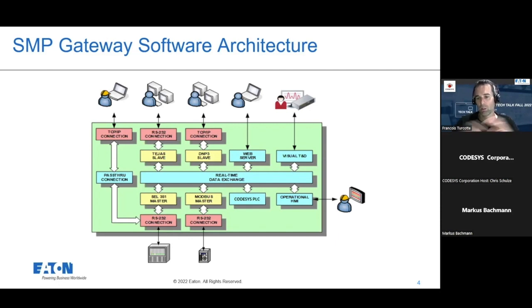The main thing that this device does is concentrate all of these value tags and translate them from one protocol to another, or send them to an HMI. It's really just a big box that manages tag or point values for representation. For example, you take masters, pull information, send it to the real-time data exchange, or RTDX, and send it back to a slave, which you can see as a server.